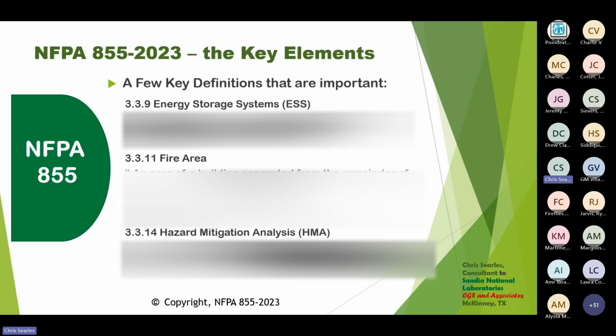Hazard mitigation analysis: evaluation of potential energy storage system failure modes and the safety-related consequences attributed to the failures. I meant to say at the beginning of this that this is, in my mind, one of the most important definitions in the standard because it is fundamental to the actual creation that allows, whether you're a manufacturer, a developer, an installer, or an AHJ, approving the installation of, or getting involved with, an energy storage system. This document is the basis that goes into understanding the 9540A testing that you would do that allows you to get your 9540 certification. And it is referenced heavily in the 855 standard and is referenced in NFPA 1, not necessarily IFC yet. We'll talk about that later.